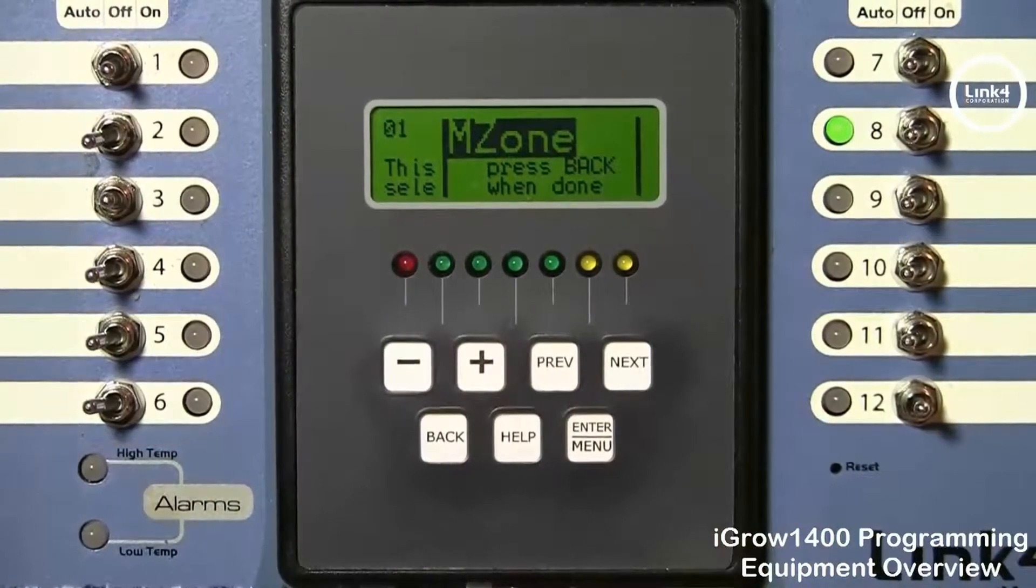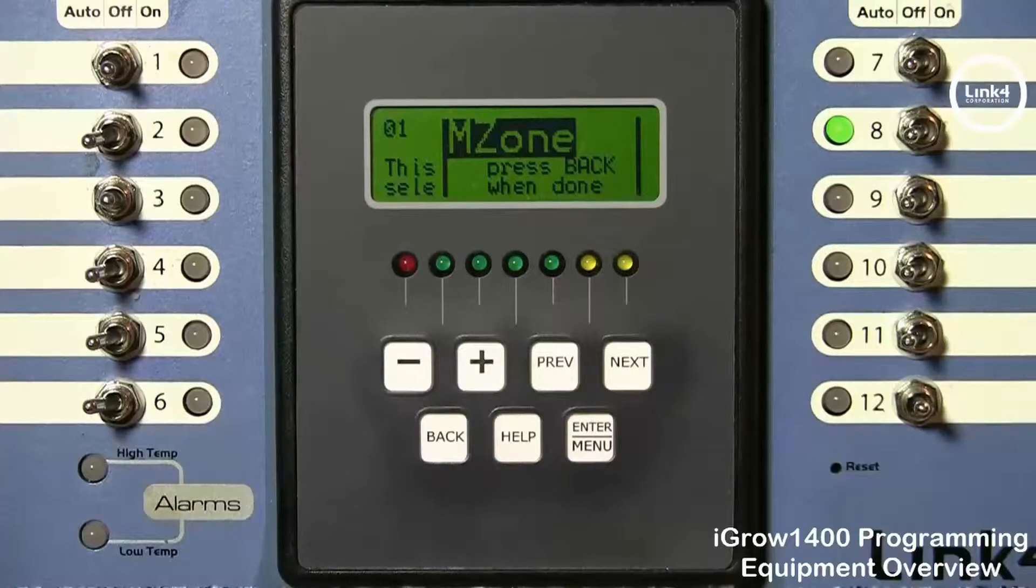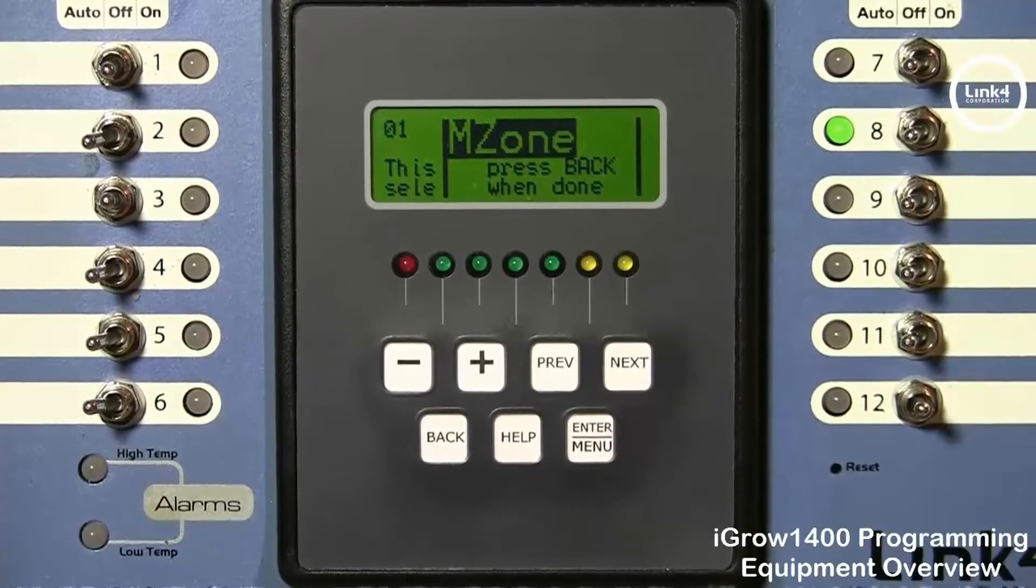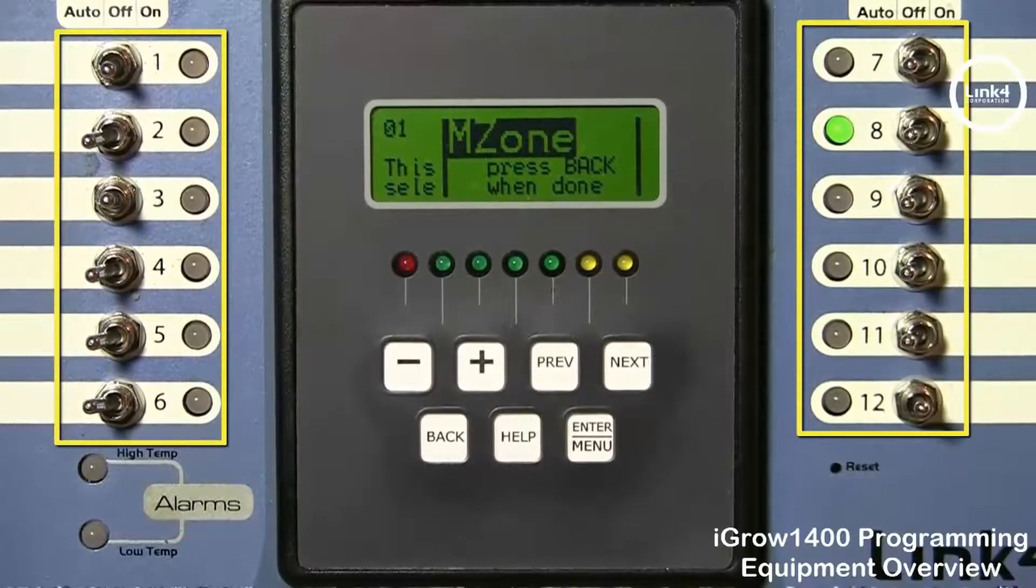You have M zone or micro zone which is an on off type device with its own set points and temp sensor probe only. It is an independent thermostat output with day night settings and it can be programmed on any channel.